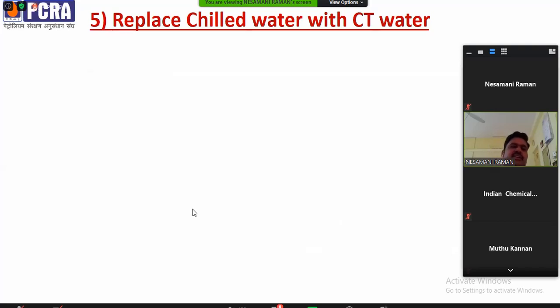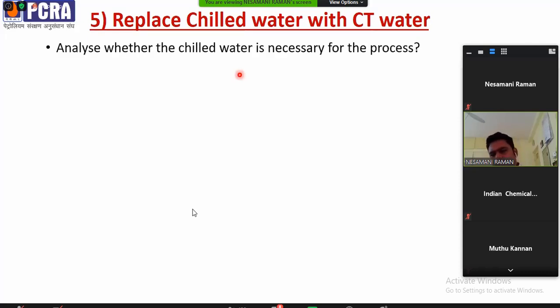And the fifth important thing is the method of replacing chilled water with cooling tower water. In most industries, particularly automobile industries, during the audit we have observed that they have molding machines, and for cooling them they use chilled water at 9 degrees Celsius. But we need to analyze whether chilled water is necessary for the process or equipment. Because if you see the OEM manual, a temperature of 25 to 30 degrees Celsius may be enough, but for extra security they give highly chilled water.